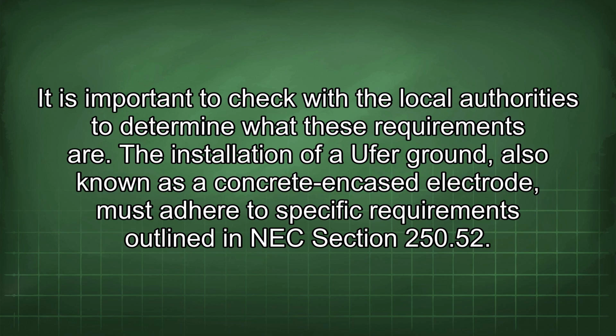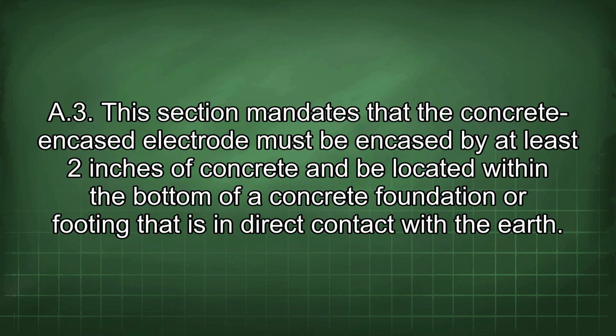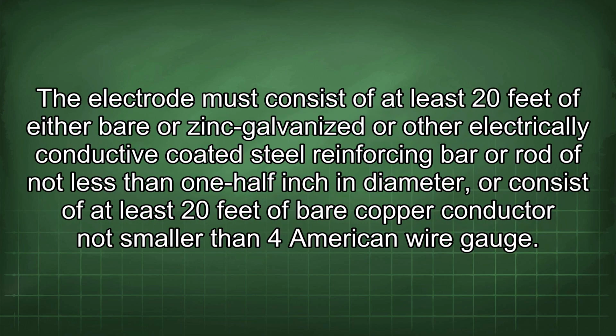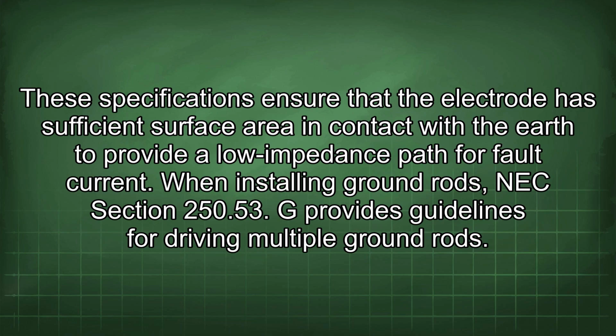The installation of a Ufer ground, also known as a concrete encased electrode, must adhere to specific requirements outlined in NEC section 250.52(A)(3). This section mandates that the concrete encased electrode must be encased by at least 2 inches of concrete and be located within the bottom of a concrete foundation or footing that is in direct contact with the earth. The electrode must consist of at least 20 feet of either bare or zinc galvanized or other electrically conductive coated steel reinforcing bar or rod of not less than 1/2 inch in diameter, or consist of at least 20 feet of bare copper conductor not smaller than 4 American wire gauge. These specifications ensure that the electrode has sufficient surface area in contact with the earth to provide a low impedance path for fault current.